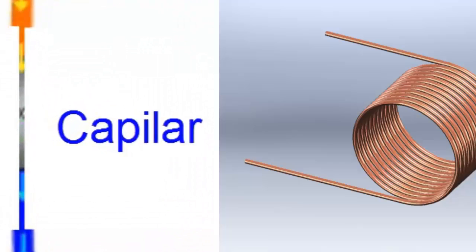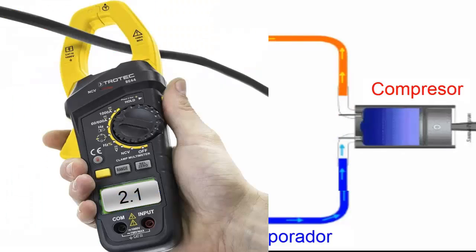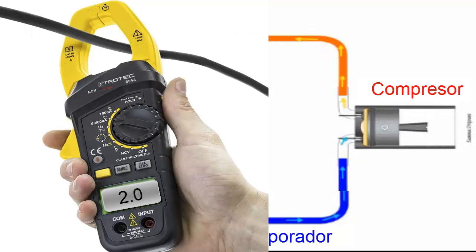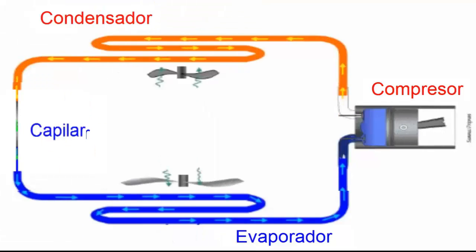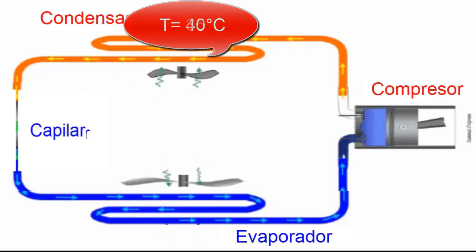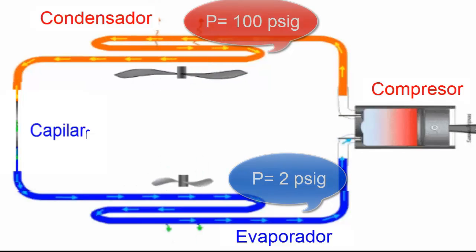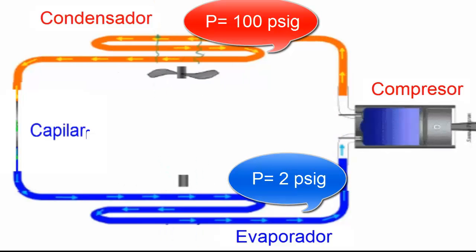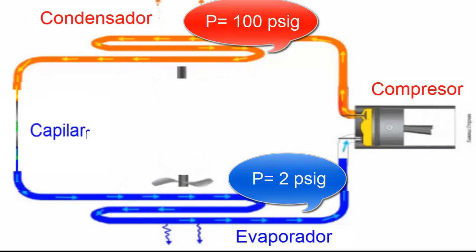8. Depending on the location of the obstruction, there may be signs of freezing at the capillary tube outlet. The condenser loses temperature and gradually approaches ambient temperature. The compressor's amperage consumption also decreases. 11. This behavior indicates how a system responds to an obstruction: a decrease in low pressure, a peak in high pressure, and eventual stabilization with lower pressures, along with signs of freezing, changes in condenser temperature, and a decrease in compressor amperage consumption.